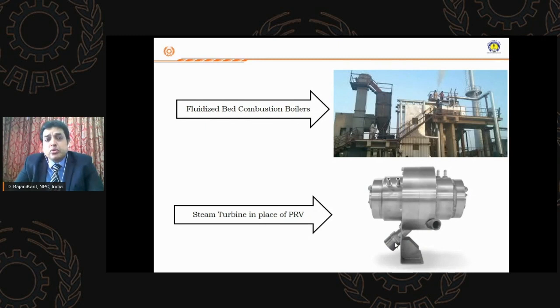You have these fluidized bed combustion boilers. It's a proven technology, and the advantage of this boiler is that you can use multiple fuels. You can use rice husk combined with coconut shell. You can use coal and so on. The fuel will be in the fluidized state. It has as high as 88 to 89% efficiency, and it is available from as low as 6 tons per hour to higher capacities of almost 100 tons.